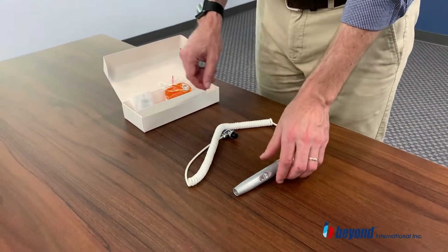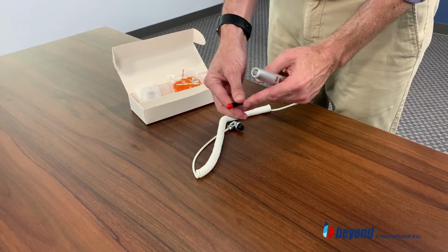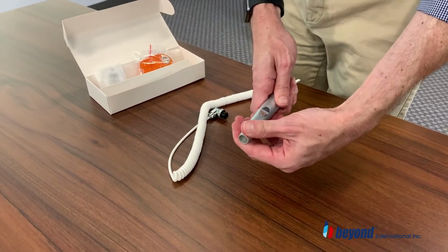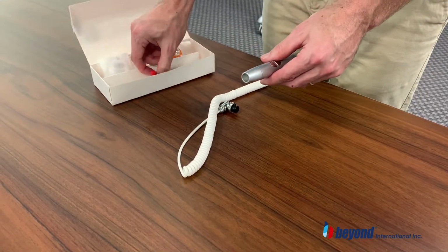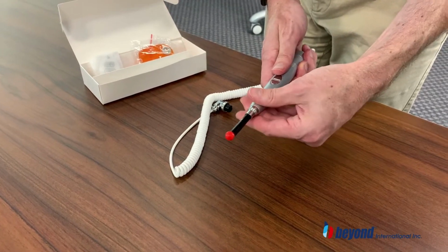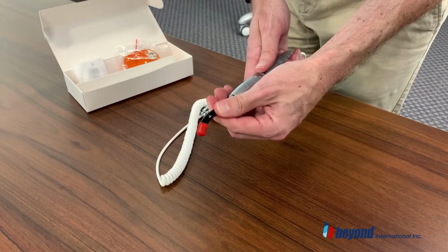All right, so now we're going to attach the curing light. So I'm going to take the tip, which is again very fragile, so I'm gonna be very careful with this. Now I'm going to attach it here. Now what I want to do is to loosen just slightly here. That's going to allow air to come through. And I'll just bring it through as so, and then I will lastly tighten here. What that does is make it much easier to put the tip on.